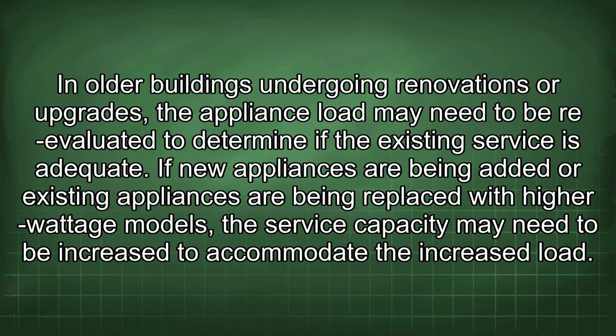In older buildings undergoing renovations or upgrades, the appliance load may need to be re-evaluated to determine if the existing service is adequate. If new appliances are being added or existing appliances are being replaced with higher wattage models, the service capacity may need to be increased to accommodate the increased load.